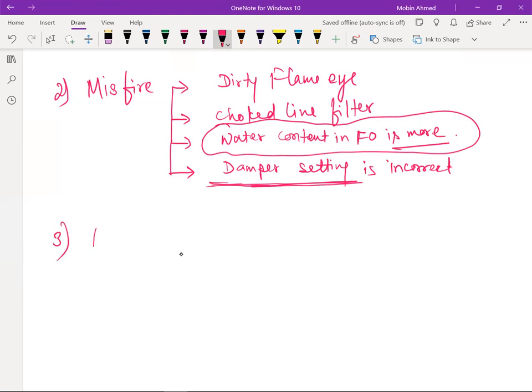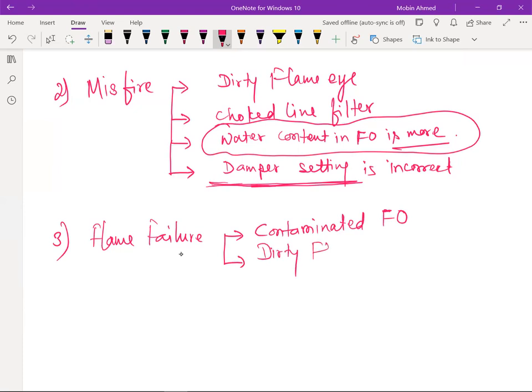Third, flame failure. Suppose the main burner has run for half an hour or one hour and suddenly the flame is gone. If this is happening, again there is a reason: we are going to have contaminated FO, fuel oil. I have written fuel oil problem everywhere because this is really a problem. Also the dirty flame eye. Yes, of course, if proper combustion is not taking place, your flame eye is also going to become dirty, and this flame failure will be there.